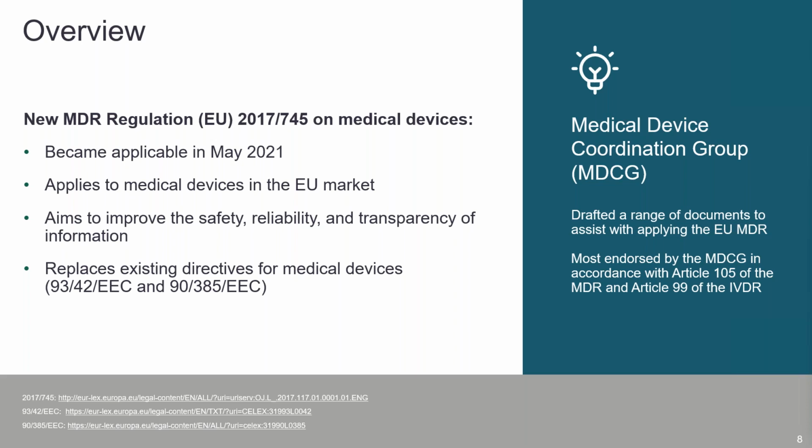So here I want to talk about the Medical Device Coordination Group, the MDCG. The MDCG drafted a range of documents to assist stakeholders in applying the EU MDR. Most documents are endorsed by the MDCG in accordance with Article 105 of the MDR and Article 99 of the IVDR. Although these documents are not legally binding, they break down the regulations and provide detailed guidance on each regulation of the MDR. So that's a good starting point in case you want to further understand or go in depth into the medical device MDR regulations.